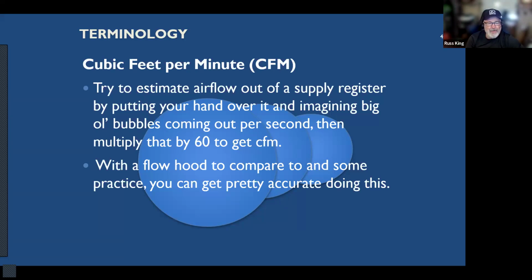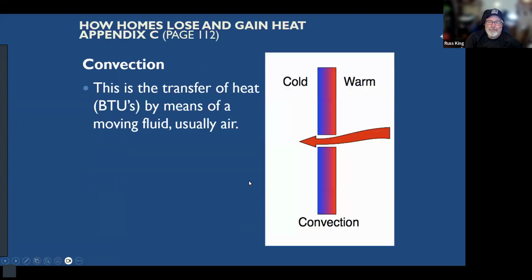And we used to get very competitive. We'd go out and measure airflow, and we'd say, okay, everyone, put your hand over the register and guess what it is, and then we'd put the flow hood over and measure it, and we got pretty darn close after doing that for quite a while. We could get within 10% or so of the airflow by putting our hand over it. So it's a fairly intuitive thing that you can get pretty good at. Okay, so that was airflow.